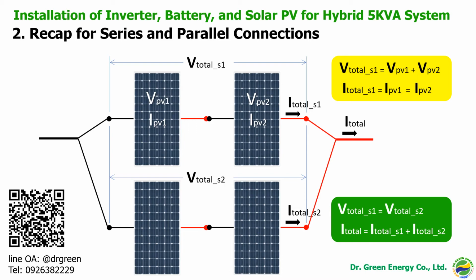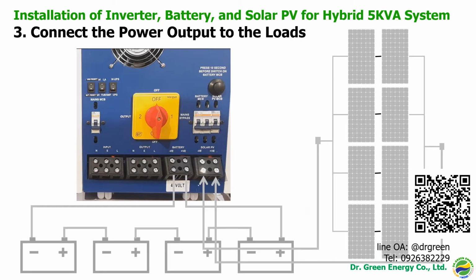We have to follow the specification of this inverter. So the third step, once you've connected the battery and finished connecting the solar panel, now you can prepare to power on the system. Press this button to safely power on, because when connecting a big system, for example a 5 kVA system, there might be a large current coming out from the battery, since sometimes you might connect more than one string of batteries.